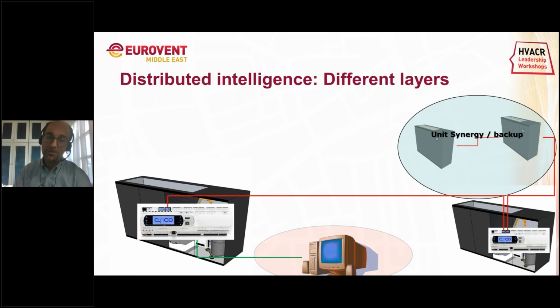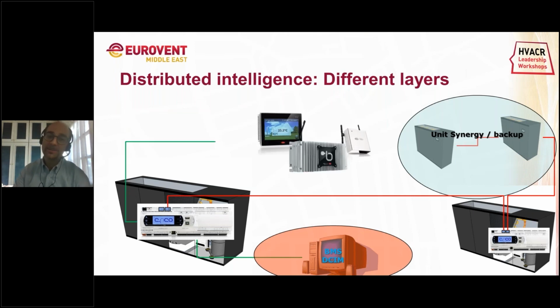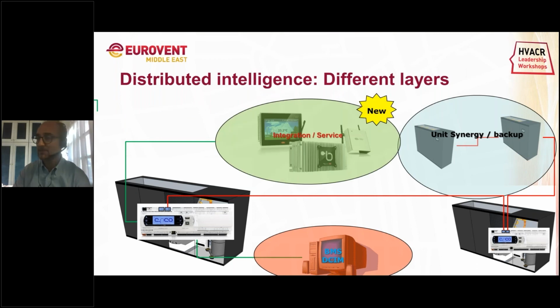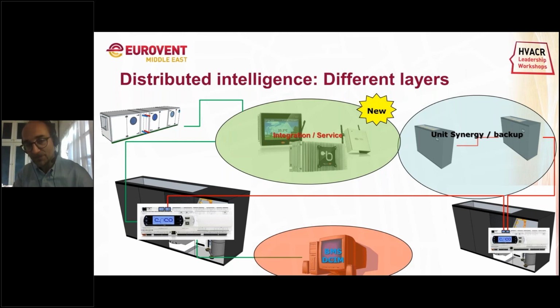That's why probably there is room now with newer technologies, so Ethernet-based multi-protocols or multi-connection, multi-serial lines to define a level that we might call integration and service. So a communication between different technologies like air handlers and CRACs to optimize the cooling part with the specific skills. Often at this level, so optimizing different technologies, it's important to have efficiency at the component level, at the unit level, and then in the end at the system level. This might be also a link between the big DCIM and so the system, the centralized BMS could obtain information from this integration and service.